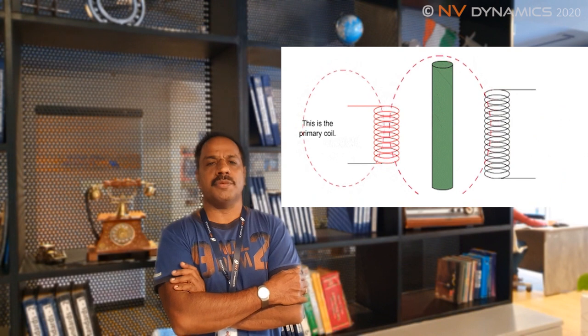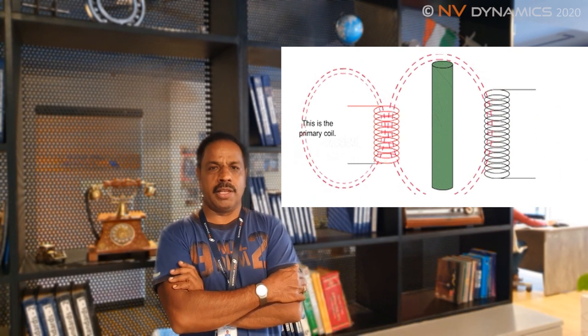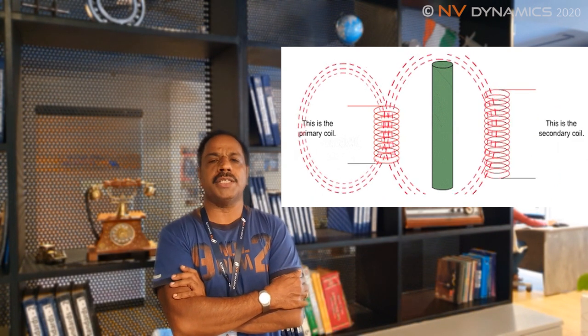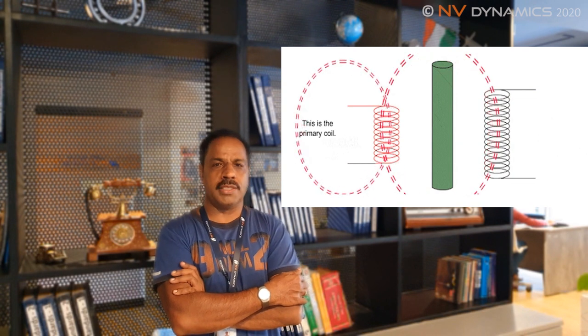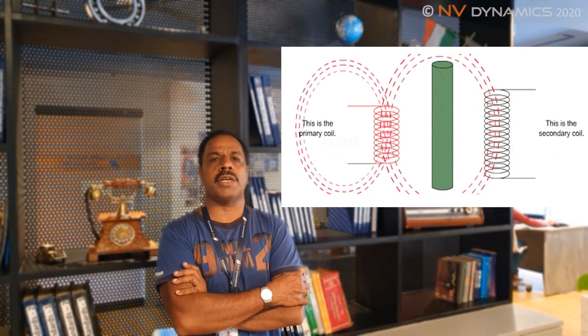The moment the armature starts moving in the vicinity of these coils, a differential voltage is generated in the two coils, resulting in a voltage proportional to the velocity of the coil movement. So by construction, even though displacement and velocity transducers may look similar, in the velocity transducer the movement of the armature is proportional to the velocity, and thus the output is measured in velocity units.